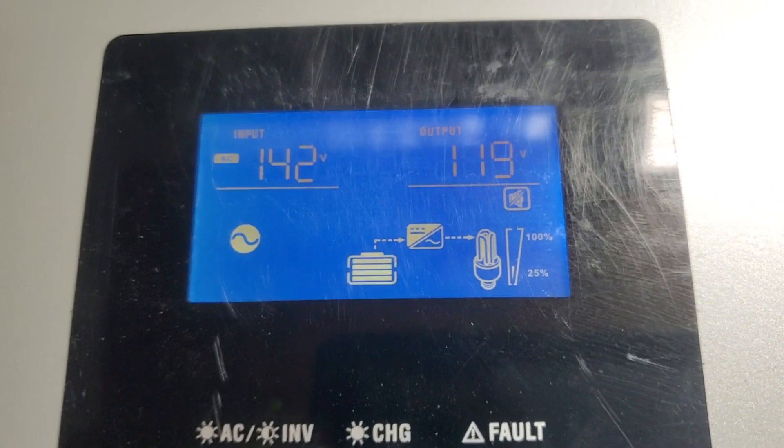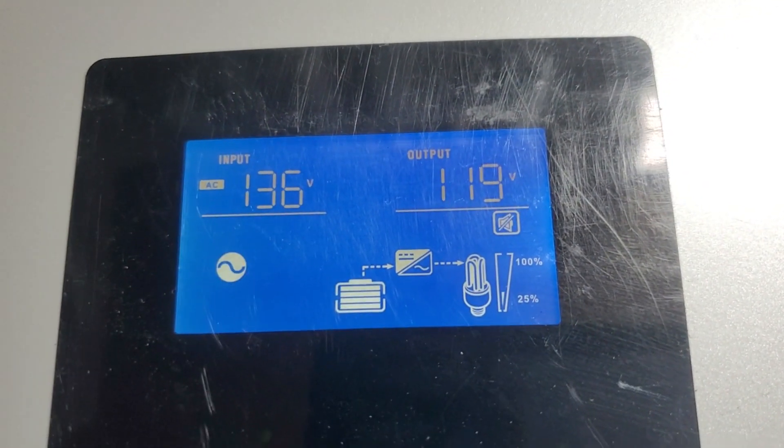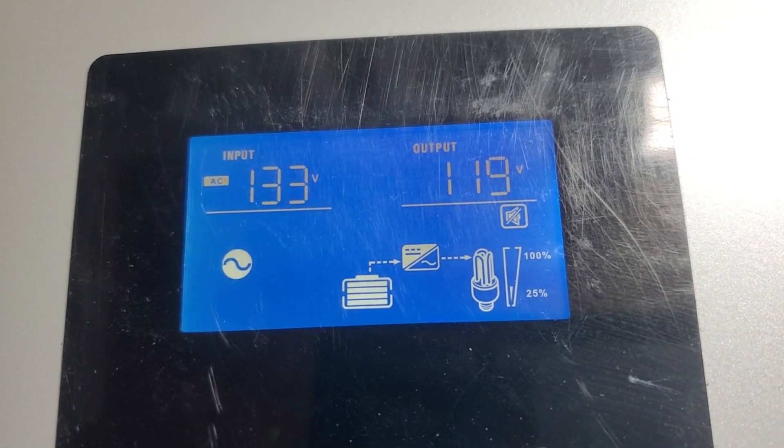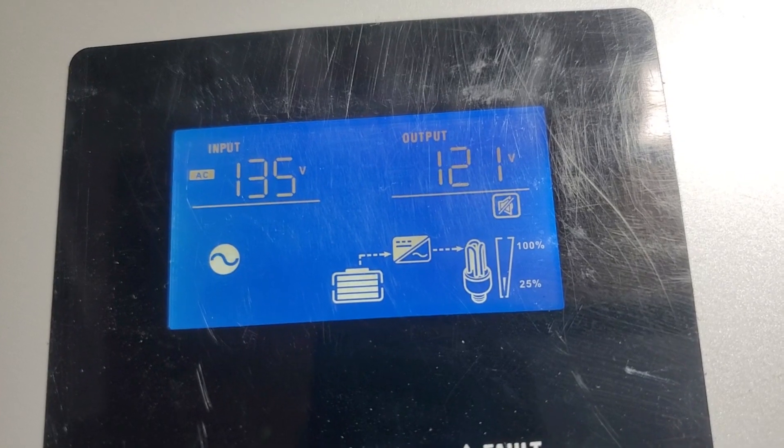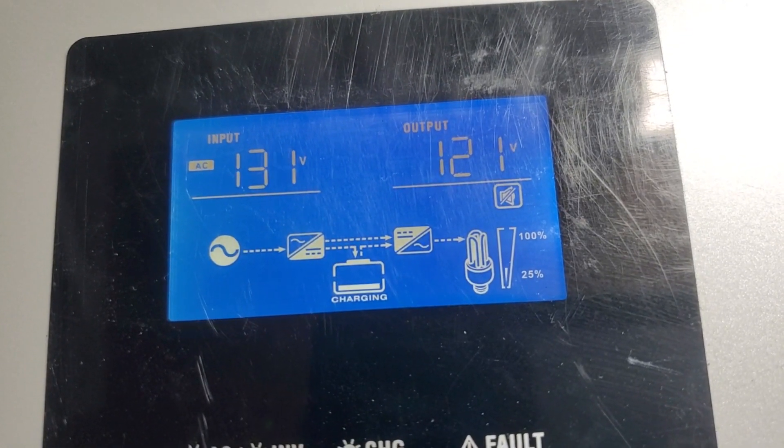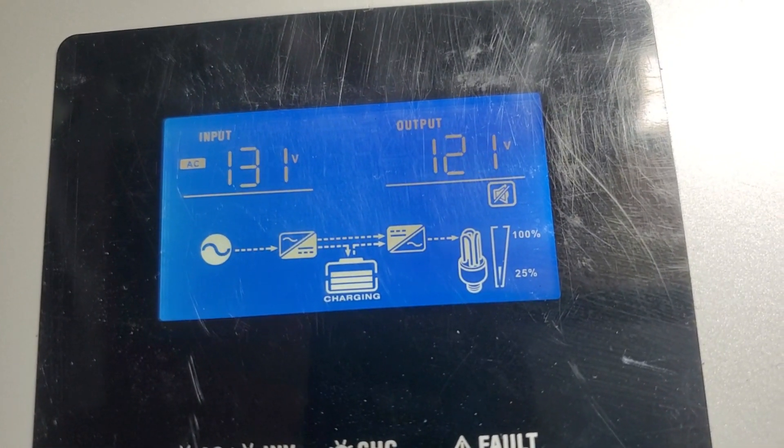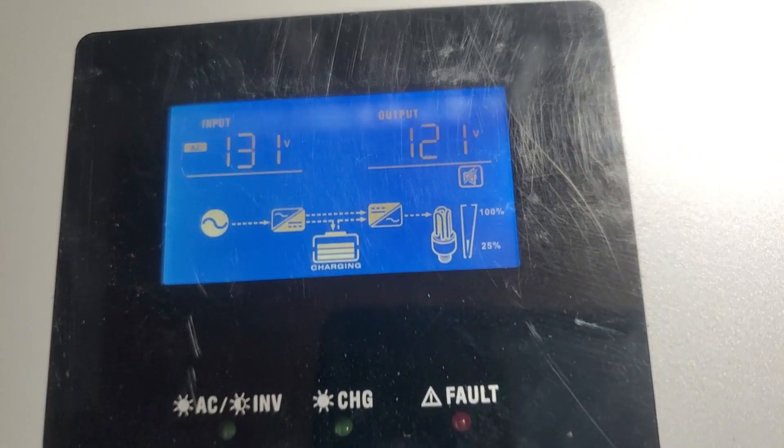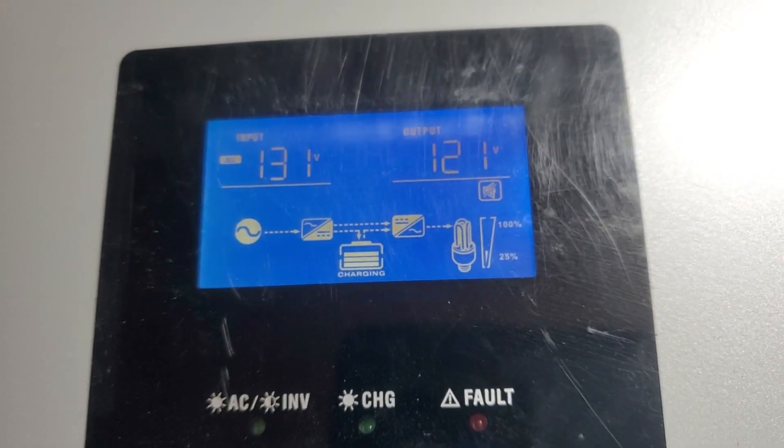And when the symbol flashes, it means the voltage is out of range. There we go. So 135V it clicked, means that it's going to accept that, and it's busy charging the battery at the same time. Okay, so it has a voltage range from about 90 to 135V.